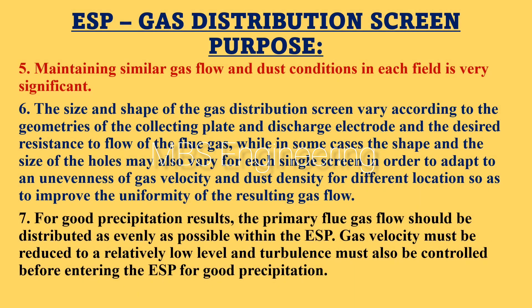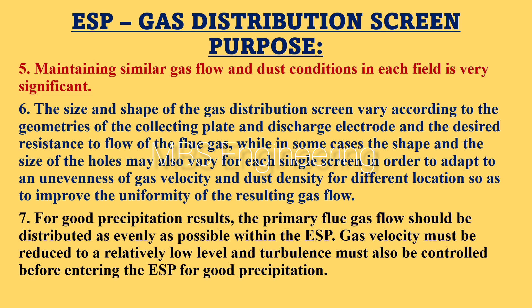Point 5: maintaining similar gas flow and dust conditions in each field is very significant. Point 6: the size and shape of the gas distribution screen vary according to the geometries of the collecting plate and discharge electrode, and the desired resistance to flow of the flue gas. In some cases, the shape and size of the holes may also vary for each single screen to adapt to unevenness of gas velocity and dust density at different locations, improving uniformity of the resulting gas flow.